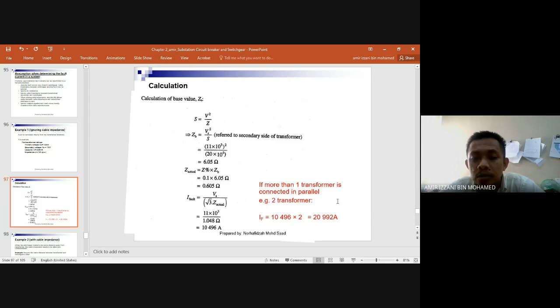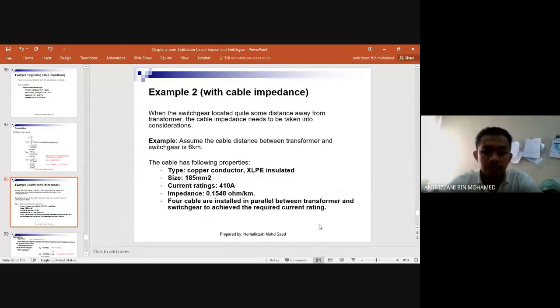Okay, a little note here. If more than one transformer is connected in parallel, for example 2 transformers, we need to multiply by 2, like what happened in our substation that I showed you just now. We have 2 transformers, so we multiply by 2 and we get the fault current for 2 transformers. Okay, second example.